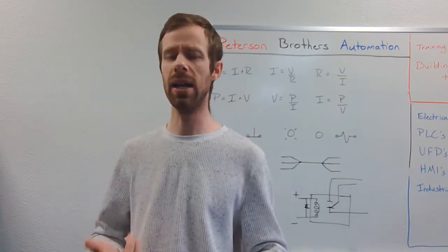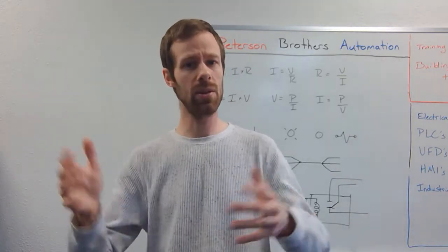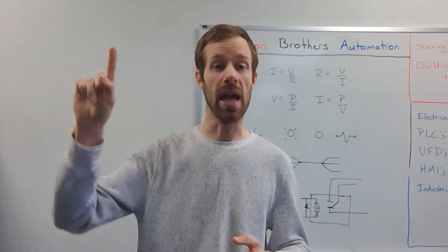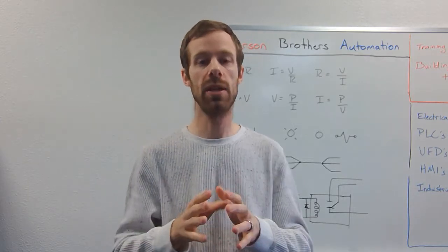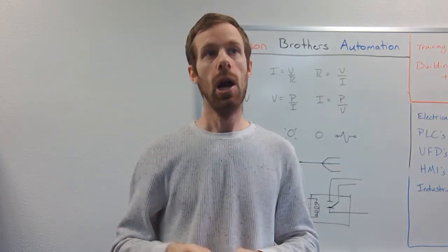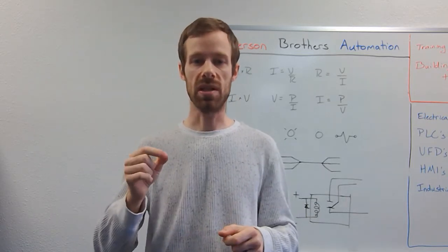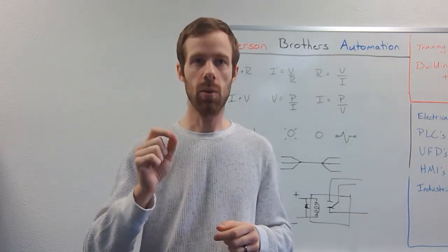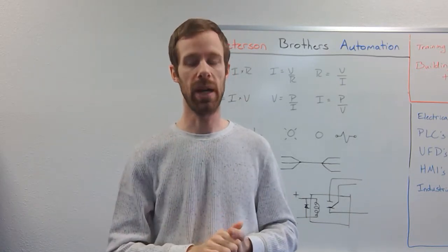Not only the cost of the wires, the cost of the switches, the extra breakers, the size of the panel that you'd need. So instead, we come from a circuit breaker and come to a junction box, and then we split off from there, which means that if this is the case in a parallel circuit, we're going to see a wire nut with at least 3 wires underneath it. If you see that, you know that the configuration is parallel.